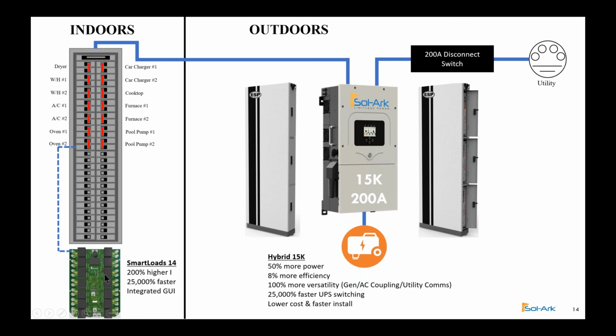The way the SmartLoad works is kind of an interrupt style. You go to a circuit, say the dryer breaker, disconnect it, run wires down to the first circuit of the SmartLoad, then run them back up to that breaker. Then you do the water heater, air conditioning 1, air conditioning 2, etc. You do that for the top 14 circuits in your panel.